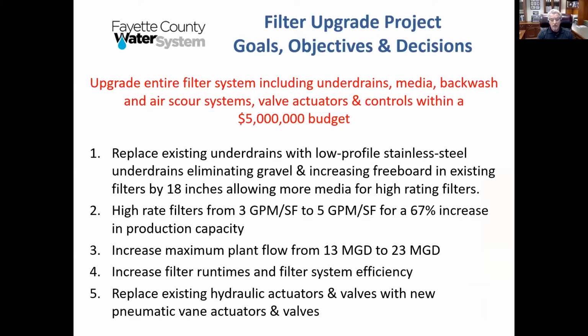They ended up rebuilding these filters to high rate the plant from 3 gallons per minute per square foot to 5 gallons per minute per square foot. That's the translation between 13 MGD and 23 MGD, a 67% increase in production capacity for this plant.